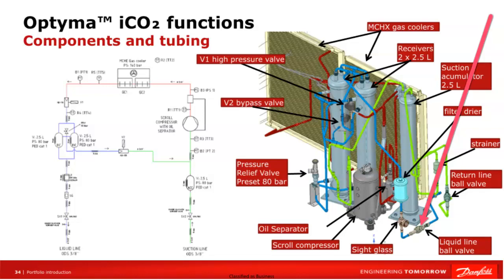These drawings are also included in the unit documentation, where pressure transducers, temperature sensor, and other important components are described in detail. Thanks to this information, the installer can better understand and operate the condensing unit, which translates into efficiency and reliability of the operation.